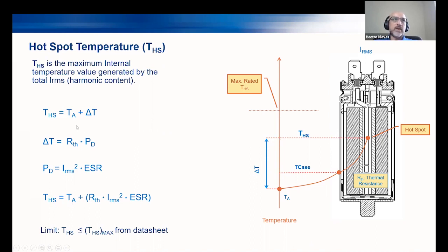So it's the ambient temperature surrounding the capacitor plus the delta T that you see between the ambient and the hot spot condition. This is the total hot spot condition, see here. This is a summarized way to do it.